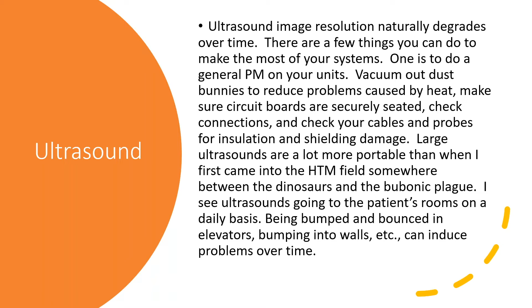Okay, let's see. Vacuum out the dust bunnies, reduce problems caused by heat, make sure the circuit boards are securely seated. Check connections, check your cables and probes for insulation and shielding damage. When I got into medicine, back, up hills both ways in the snow, ultrasounds didn't go anywhere. They brought the patients to the ultrasound. Now ultrasounds go everywhere, on elevators, off elevators, bumpity, bumpity, bump, and this can cause all kinds of little intermittent problems. Being bumped and bounced daily induces problems over time. So in your PM procedure, make sure everything is seated: all the cables, all the Jones plugs, all the circuit boards. It will take you 10 minutes, but it will definitely pay in benefits for all those little gremlins.